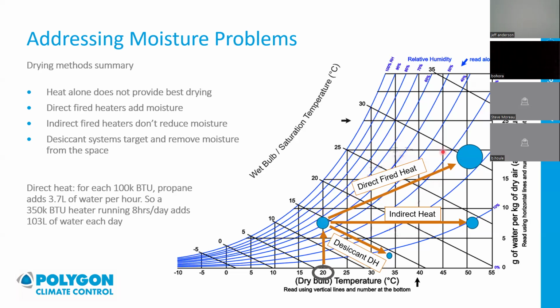So if we use a direct fired heater, now I mentioned that I would explain this. A direct fired heater is going to be a gas fired heater. That could be natural gas, that could be propane. But you're basically lighting gas on fire and you're taking air and pushing it through that flame. There's no separation of the air and the flame, it's just flowing through it. It's taking all the products of combustion and moving them right into the space you're using them.